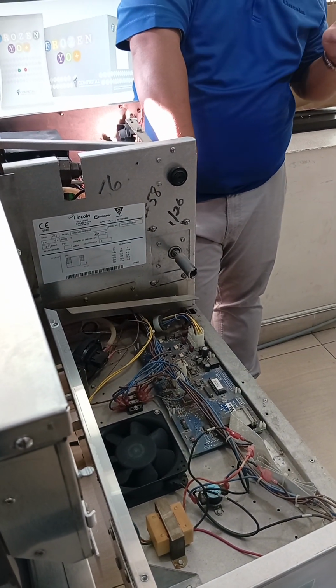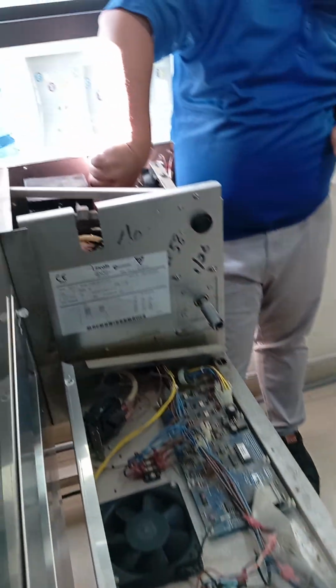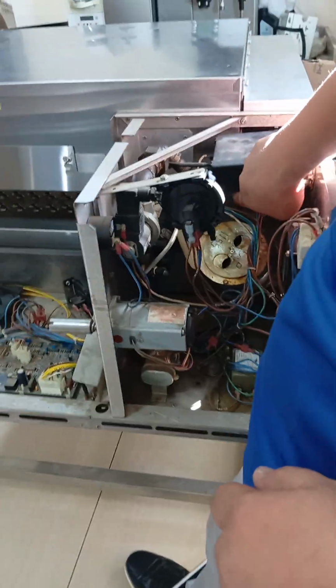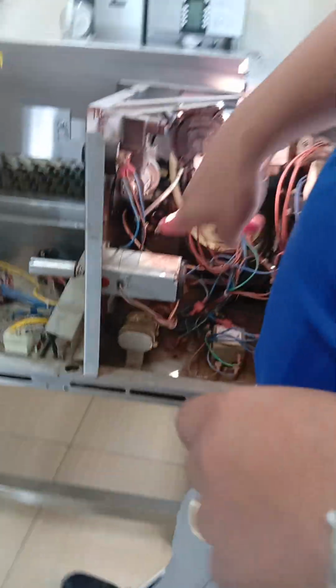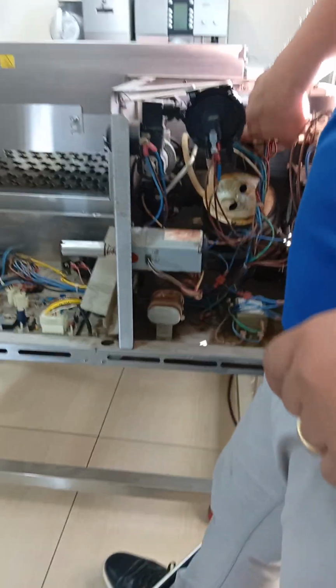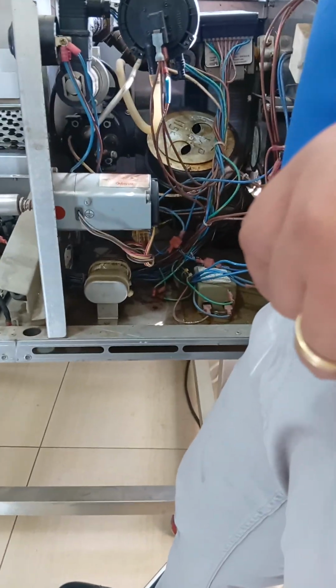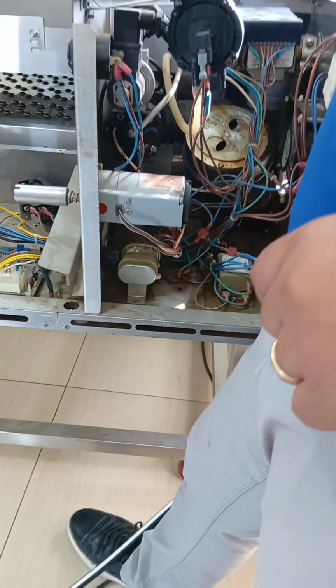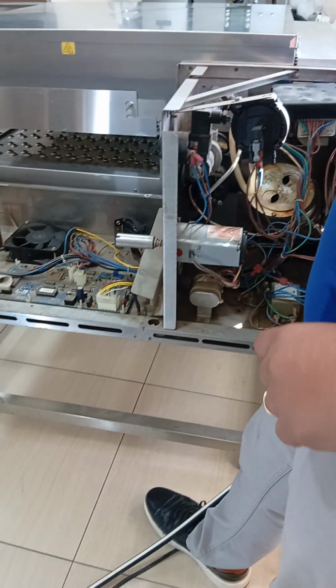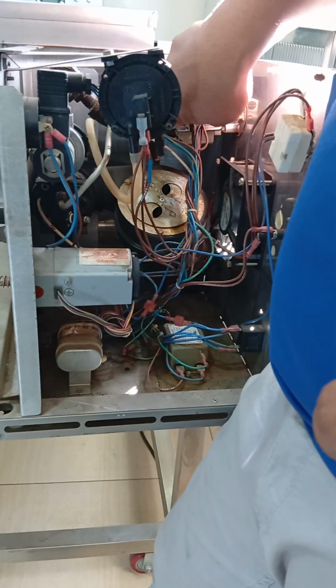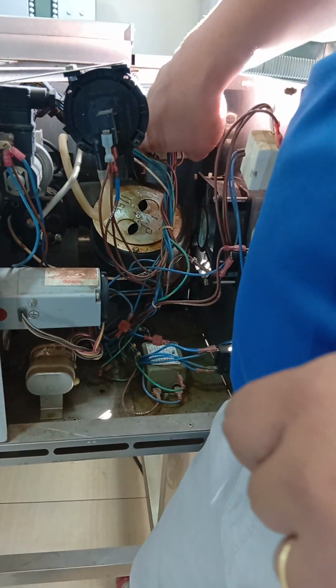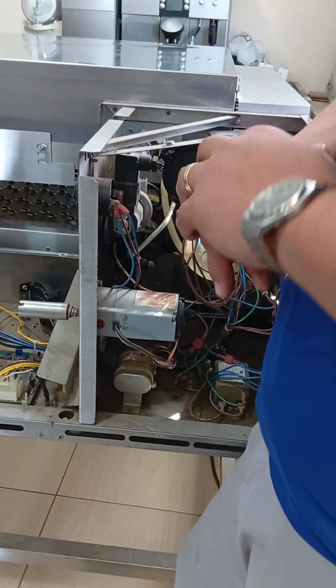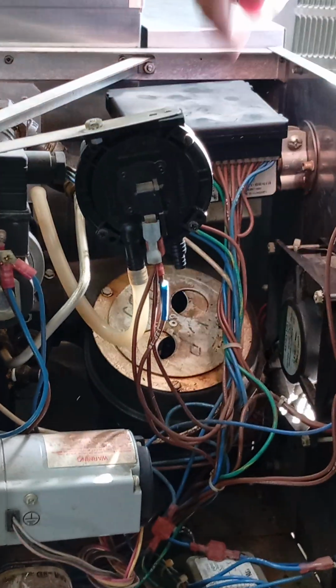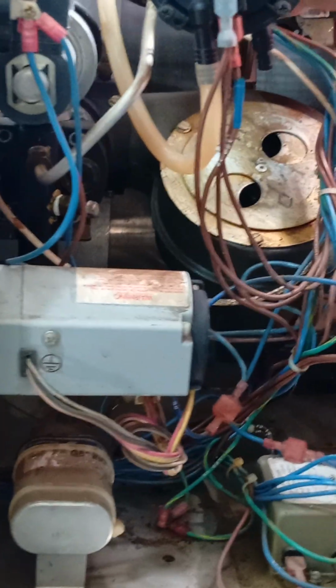How to adjust your burner pressure? So we have the gas valve here, and you need to open this cap while your meter is connected. Open the cap, you will see the adjustment. Adjust slowly. And after you adjust, the most common thing a technician forgets is to return the cap. Make sure whatever you remove, you return it.